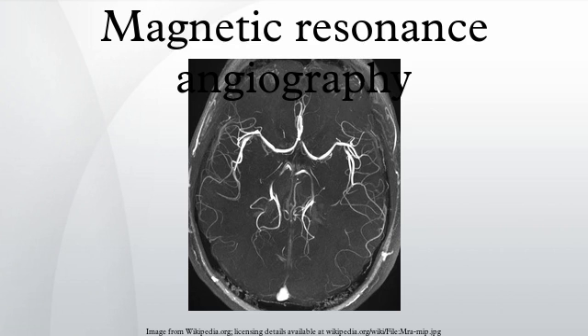Phase contrast PCMRA can be used to encode the velocity of moving blood in the magnetic resonance signal's phase. The most common method used to encode velocity is the application of a bipolar gradient between the excitation pulse and the readout. A bipolar gradient is formed by two symmetric lobes of equal area, and by definition the total area of a bipolar gradient is null. The bipolar gradient can be applied along any axis or combination of axes depending on the direction along which flow is to be measured.